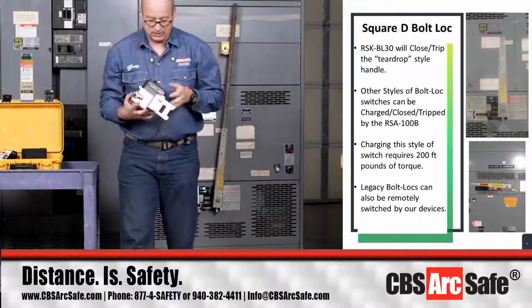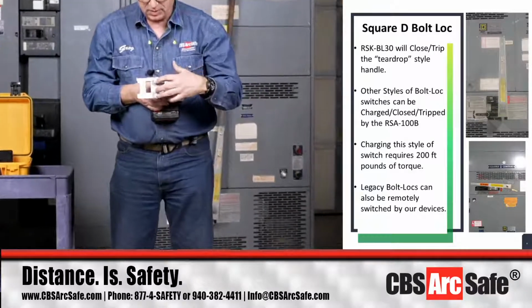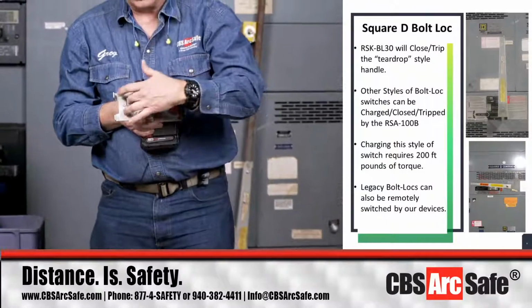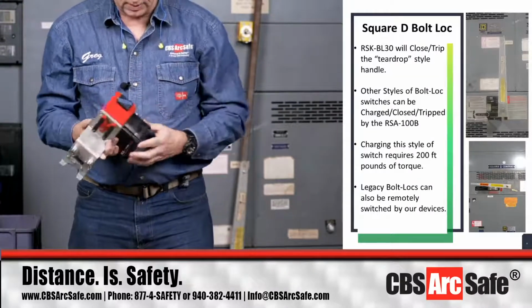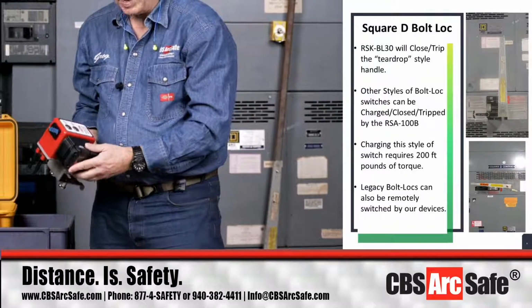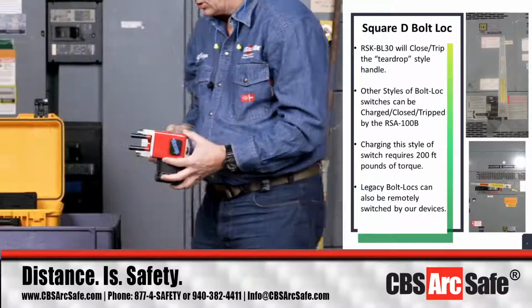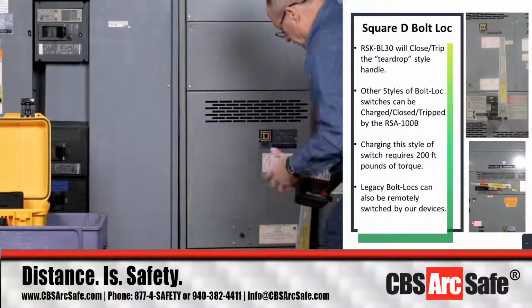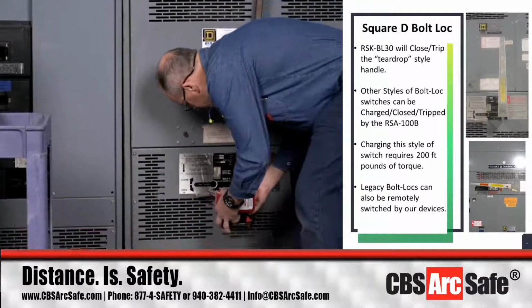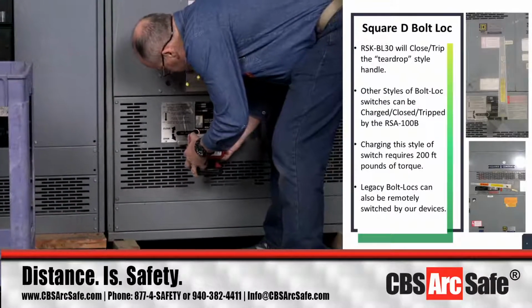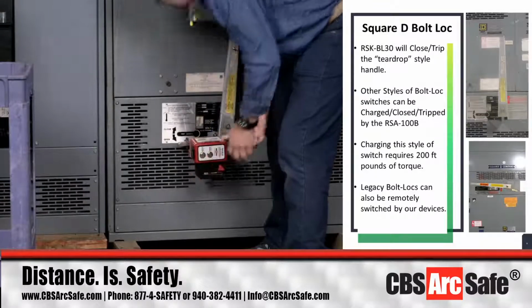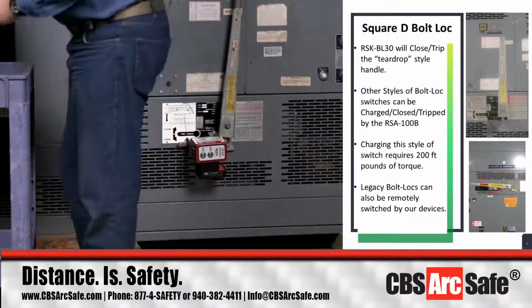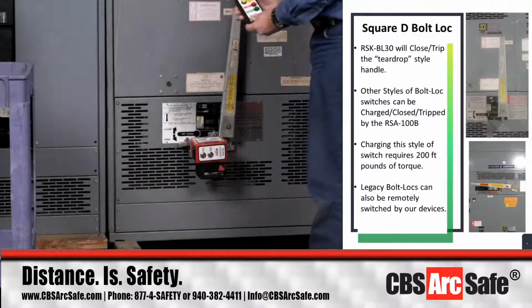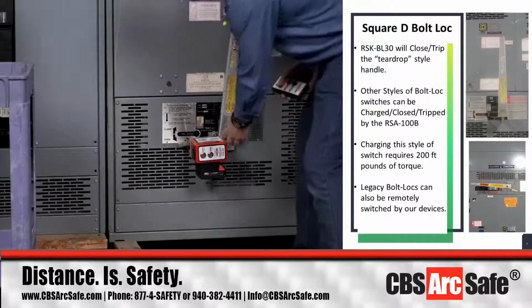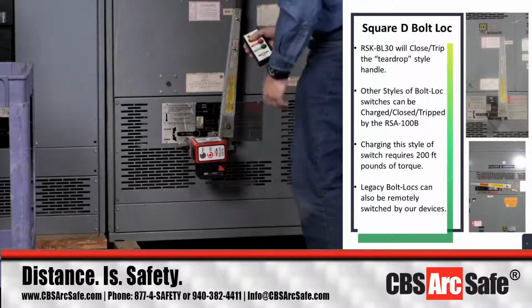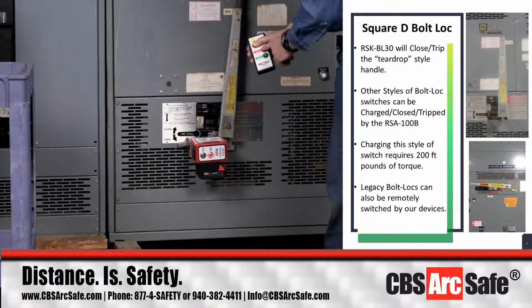Now the way this mounts is this. We've got a couple small magnets right here, our actuators, and this goes over the lockout tagout portion right there. This uses the Milwaukee battery so you can get a good distance away from it. Once you've got your springs charged, you come in and place this on here. It's going to locate on the face just like this. Then we take our press and hold and enable - we wake it up first down here. Then we can press this, and we're going to close the breaker.